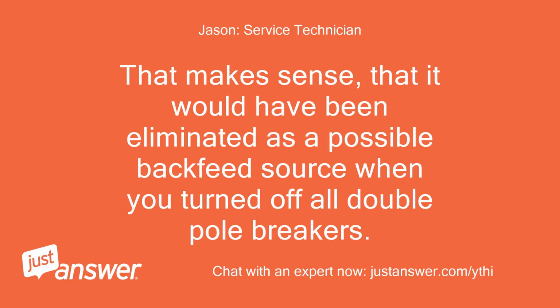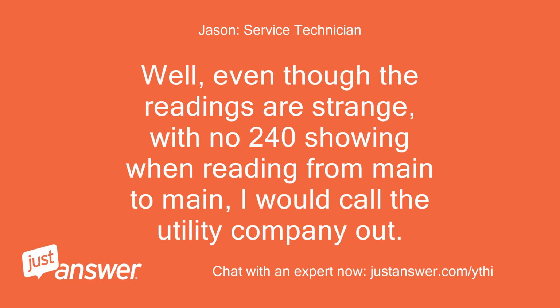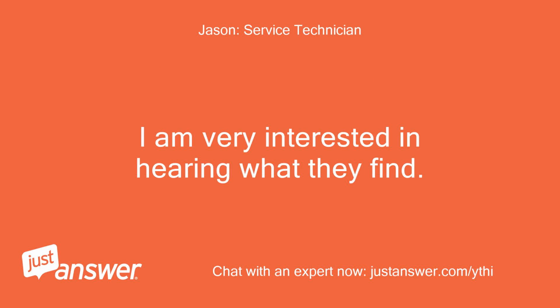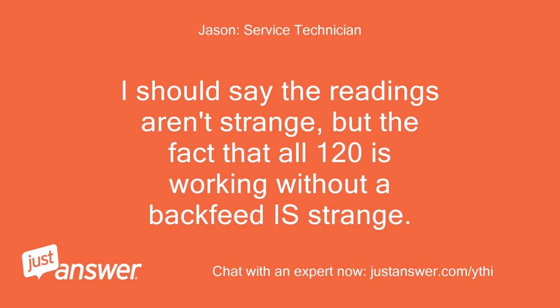That makes sense, that it would have been eliminated as a possible backfeed source when you turned off all double pole breakers. Well, even though the readings are strange, with no 240 showing when reading from main to main, I would call the utility company out. I am very interested in hearing what they find. I should say the readings aren't strange, but the fact that all 120 is working without a backfeed is strange.